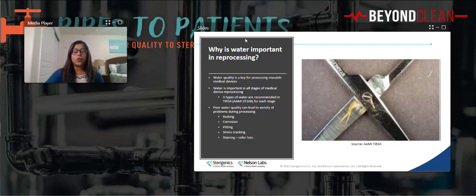Now, poor quality water can lead to rusting, corrosion, pitting, stress cracking, staining. I'm sure you've seen all of these on instruments, and you're wondering what's happening here. Is it sterilization? Is it high temperature? Is it the detergents? Are the chemicals too hard on them? What's going on? Did you ever stop and think that it might be water, right? We don't think about that. We forget the aspect of water and just move towards the harsh environment and think, oh, it has to be the disinfectant, or it has to be the sterilization pressures and temperatures that are cracking and stressing these. Sure, they definitely contribute to those portions of the device, but water also plays a huge role in maintaining these devices as well.